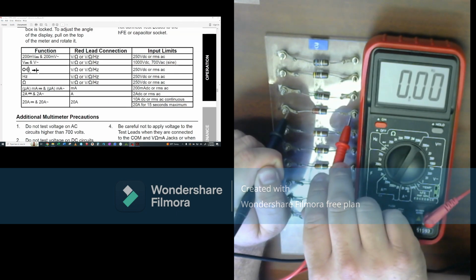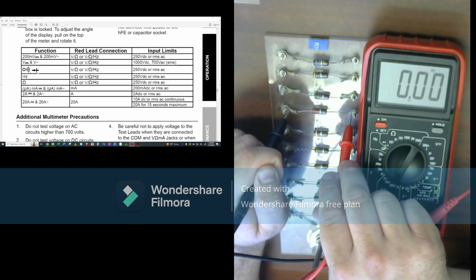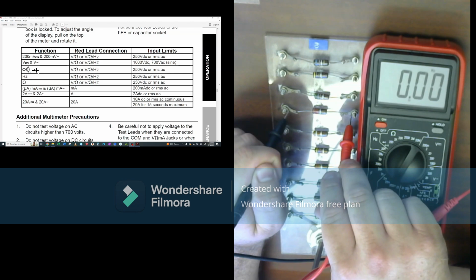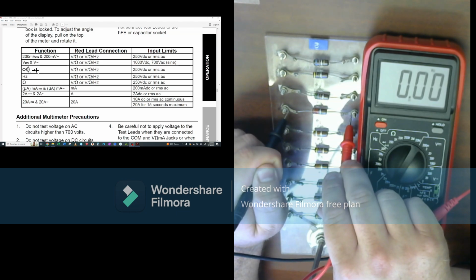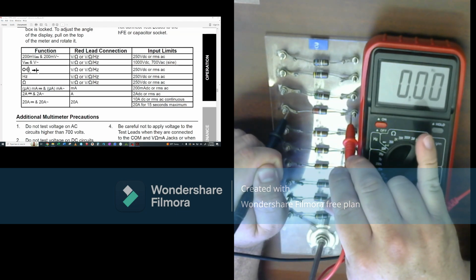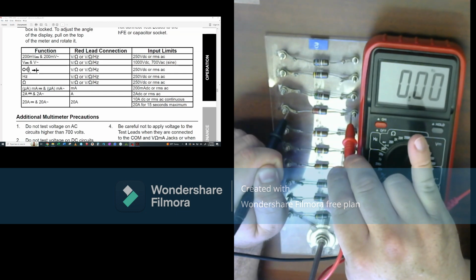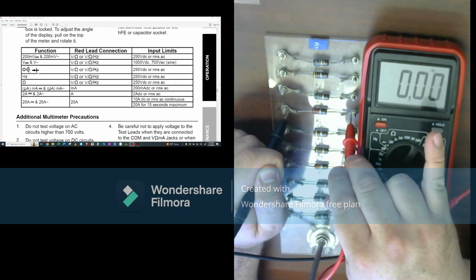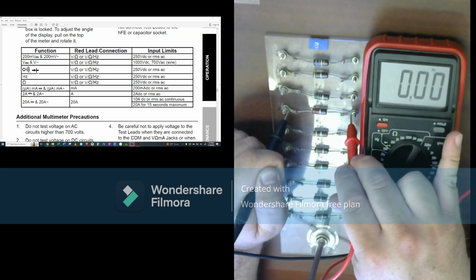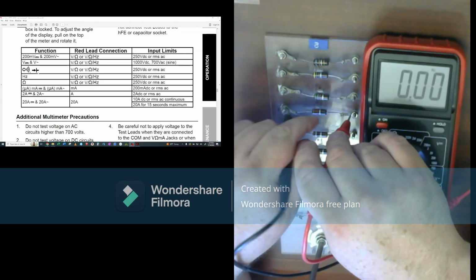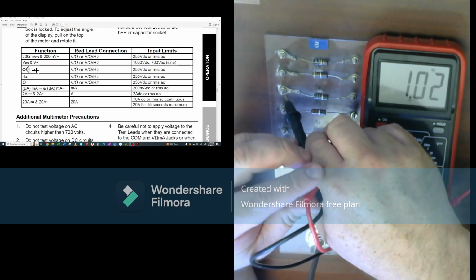If you think about it, 20 meg is how many times bigger than 1.2 kiloohms? Well, for one, it's at least 1,000 times difference because we're going from kilo to meg, 10 to the third to 10 to the sixth, so 1,000 times bigger. If we look at our screen, we're showing in decimal form. The first digit is tenths, the second is hundredths. We're already in the thousands because we're 1,000 times bigger, so we need one digit past there, and we're not even getting that. So right now we're reading way too high for the value.